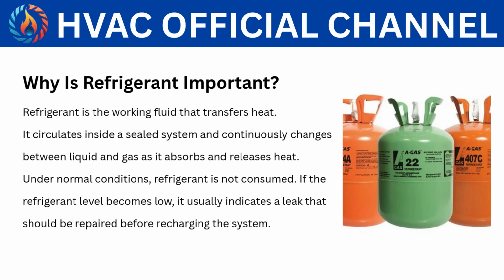Why is refrigerant important? Refrigerant is the working fluid that transfers heat. It circulates inside a sealed system and continuously changes between liquid and gas as it absorbs and releases heat. Under normal conditions, refrigerant is not consumed. If the refrigerant level becomes low, it usually indicates a leak that should be repaired before recharging the system.